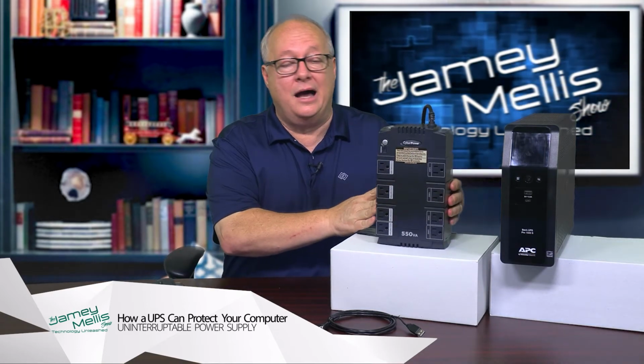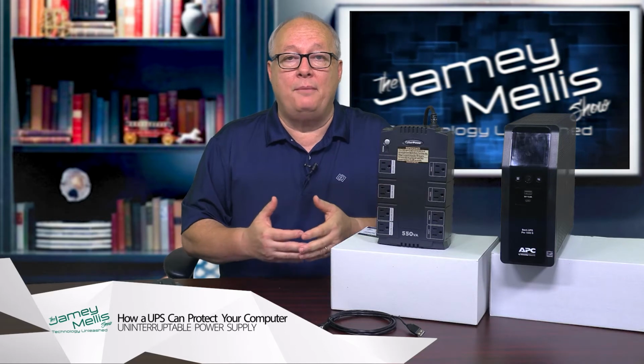If you plug in your UPS and it does not have the proper ground, that light is going to come on, indicating that you have a problem with your wiring. There could be other problems as well, and if you see that, you probably will not get the protection that you think you're going to get because of the site wiring fault.